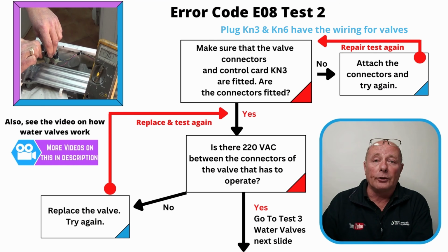Test 2 on the E08 error code is to do with the electrical system. Firstly, we need to ascertain that the wiring is in good condition going from either KN3 or your actual circuit board to the water valves, and all the wires have good continuity.